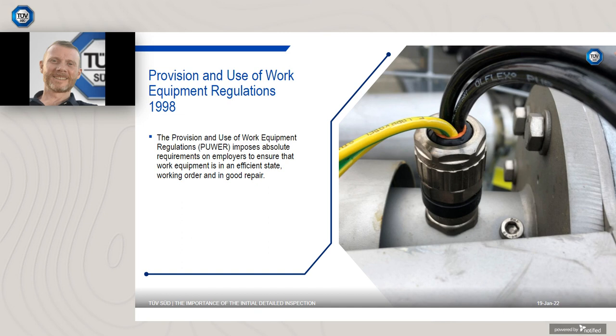This installation in the photograph was picked up at a factory pre-FAT EX inspection. The certificate for the gland states, cable gland is intended for use with an effectively filled, circular, armoured or braided cable, one cable. It also lists the components contained within the gland, which in this case have either not been used or discarded. Thankfully, this was rectified at the supplier yard prior to shipping at their cost.